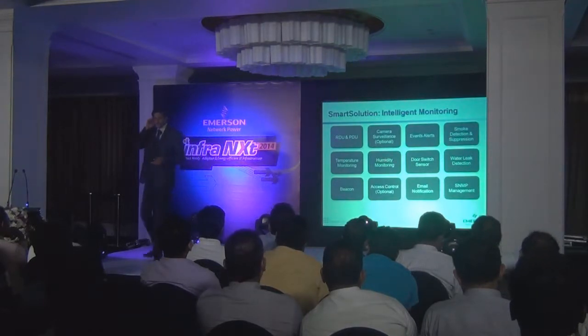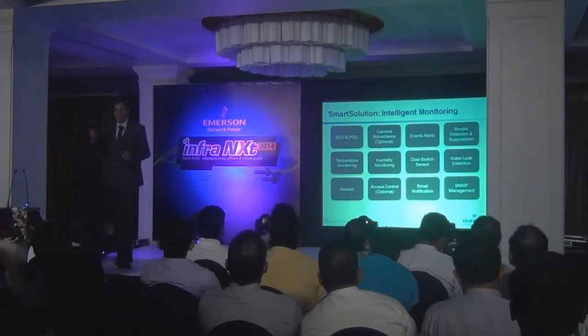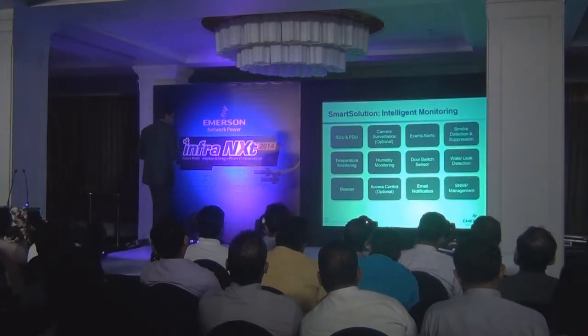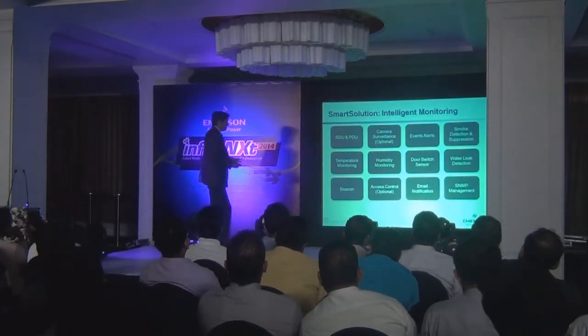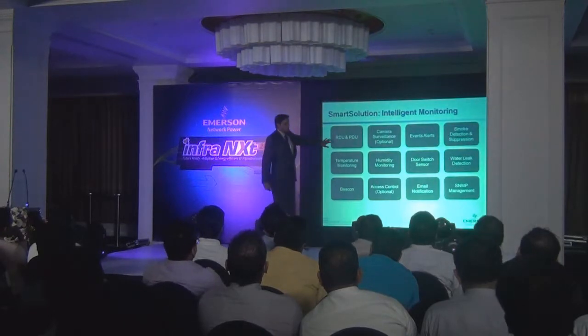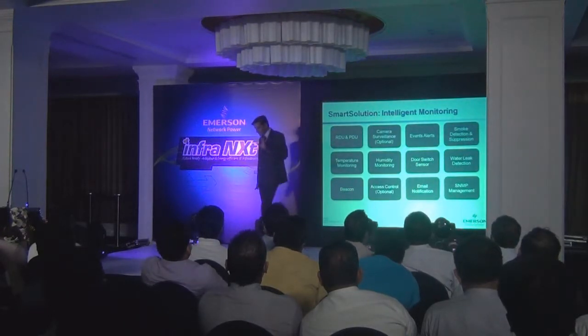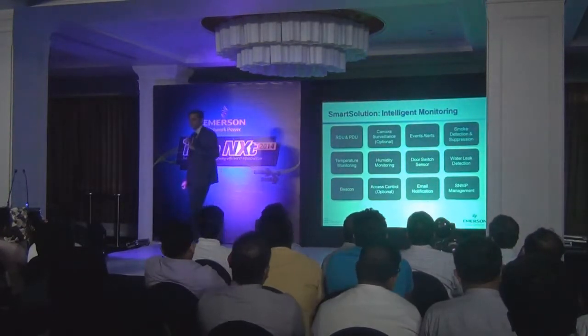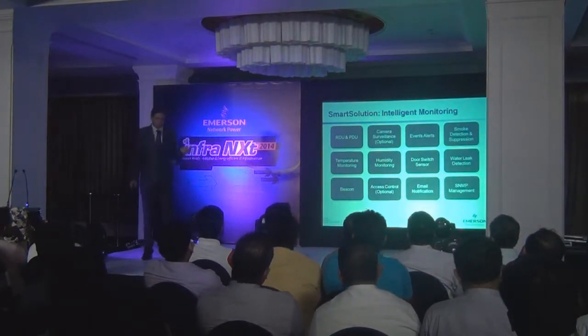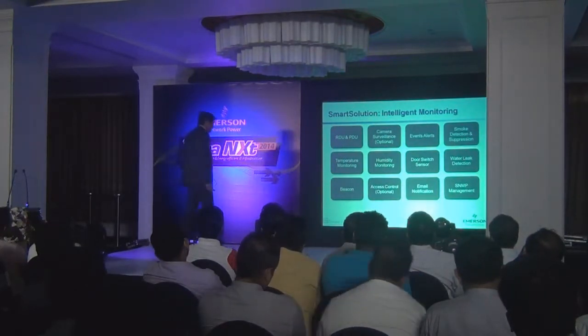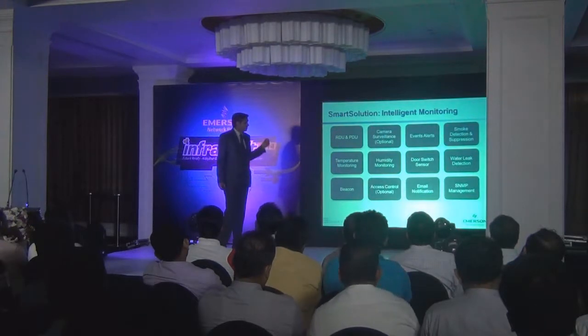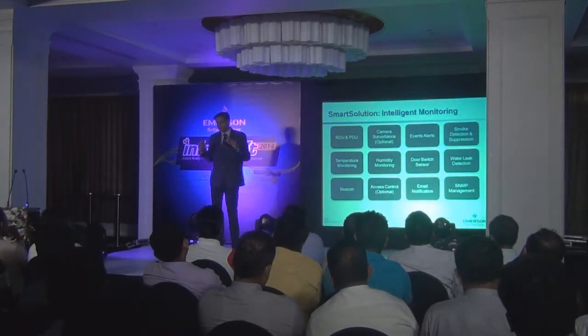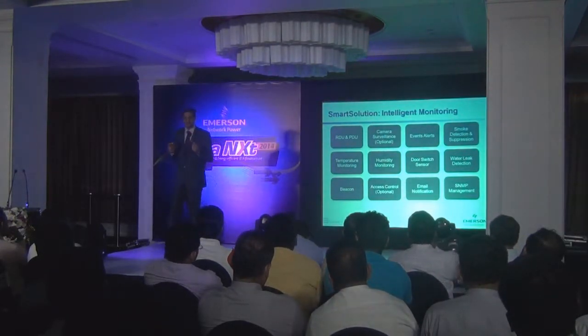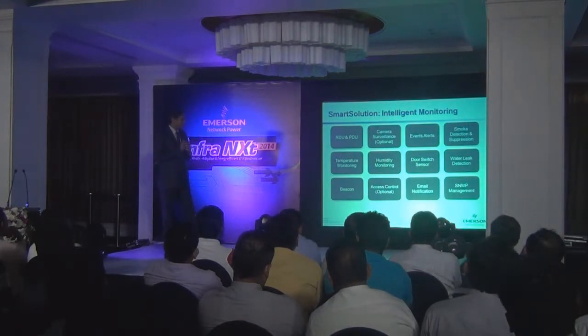From a monitoring point of view, we have a very good solution. In the smart row or smart cabinet, we provide the rack data unit and PDU. The rack data unit is typically used to monitor non-IT devices like UPS, cooling, and sensors. We also provide camera surveillance and event alerts, so if you set a threshold, you get alerts on how that equipment is behaving.